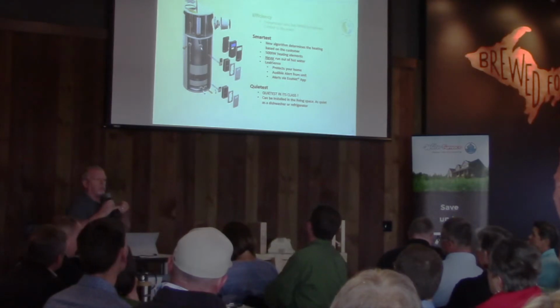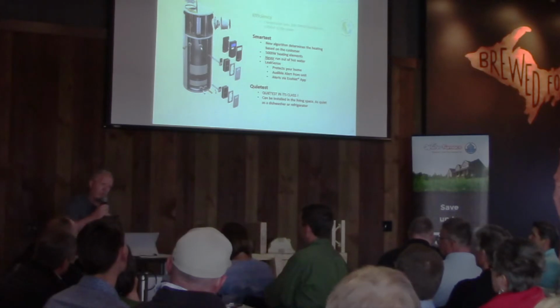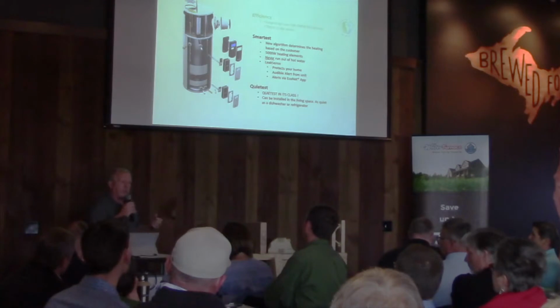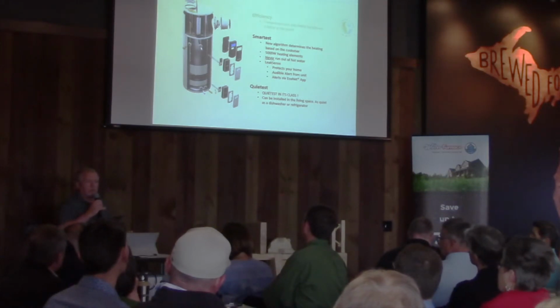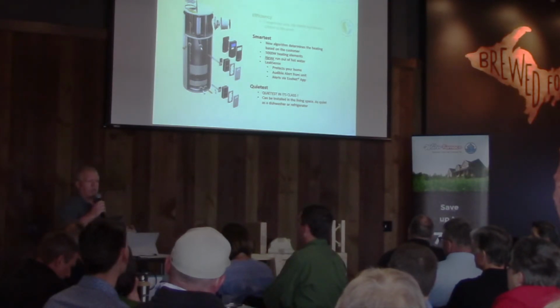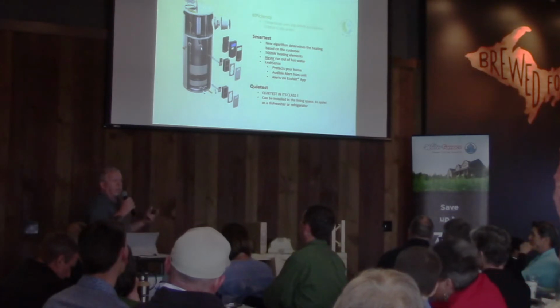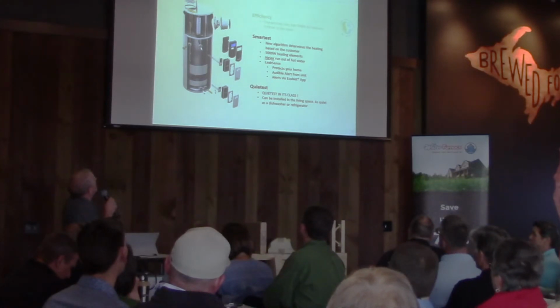I tell guys, if you're putting it on a house that's on a crawl space, duct it down into the crawl space. Pull that air up out of the crawl space, all that damp, moist, nasty air. You're dehumidifying it, you're cooling it, putting it back down there. It's going to control mold. It's going to control a lot of other issues you're going to have underneath that house. If you don't have a crawl space, you've got it on the first floor, you're in a ranch home, put it into the attic. Now you're moving air through that attic. You're cooling it, you're dehumidifying it, you're helping the house maintain. It's going to be easier to keep the house cool during the summer.